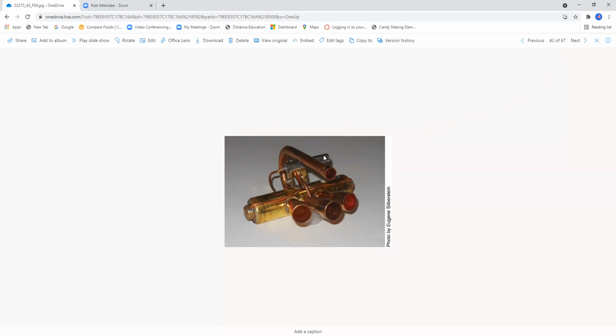Had an interesting situation in Temecula a couple weeks ago. This little capillary line right here developed a leak. I've never seen that before. And the leak was so significant that this heat pump would not operate anymore. Of course, it was out of refrigerant. And I had to use my ultrasonic leak detector. I found the leak in this pilot line right here next to the solenoid.